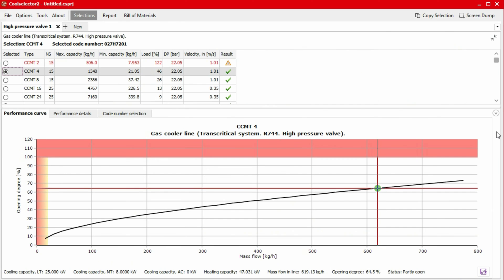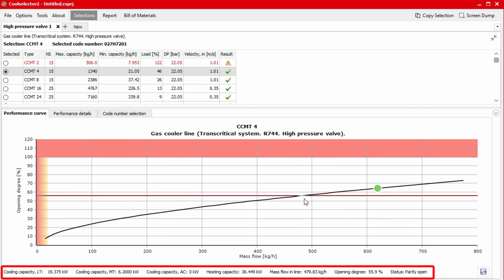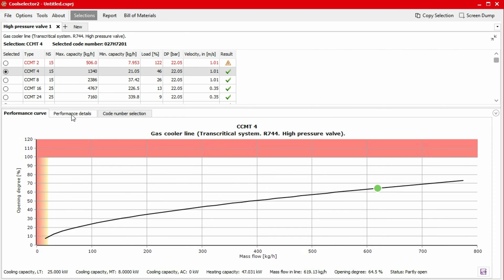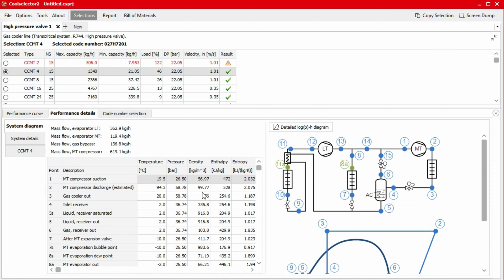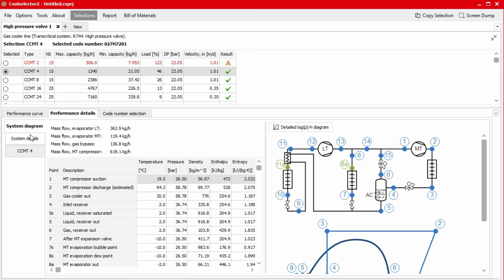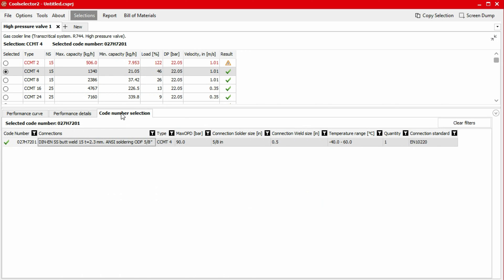To check the performance details, we head to the bottom-most segment of the window. In the first tab titled Performance Curve, we find an interactive graph plotting the opening degree against mass flow rate. The values will update as we move our mouse across the graph. Under the performance details tab, we can find thermodynamic data for the system along with a system schematic and a pressure enthalpy chart. In the sub tabs, we have system details as well as product specific data. Under the code number selection tab, we can find the code number as well as some additional product information. We can then generate a report as well as a bill of materials which can be provided to a Danfoss supplier for a quotation. We'll look at how to do that towards the end of this video.